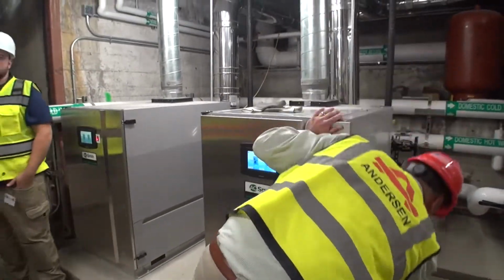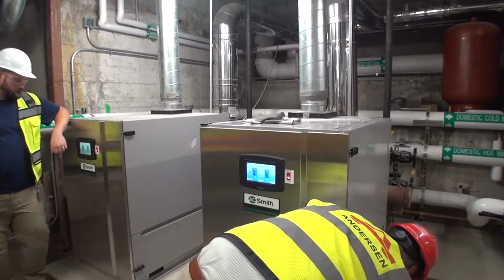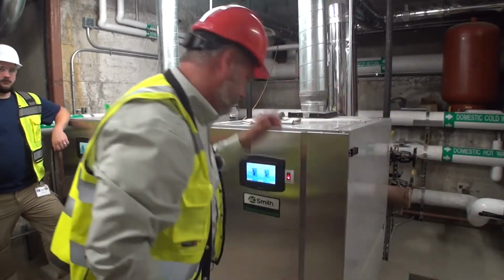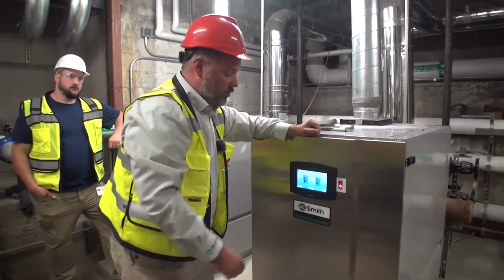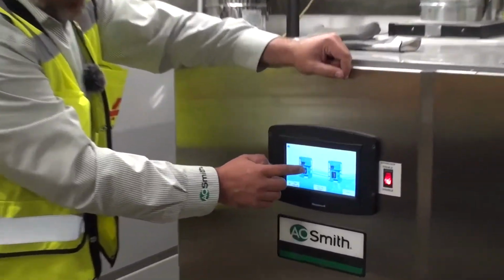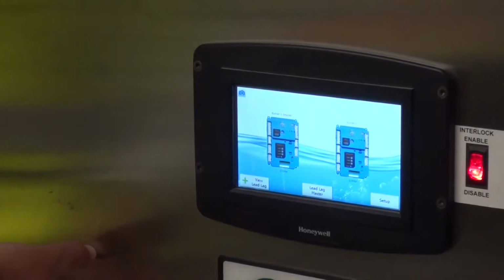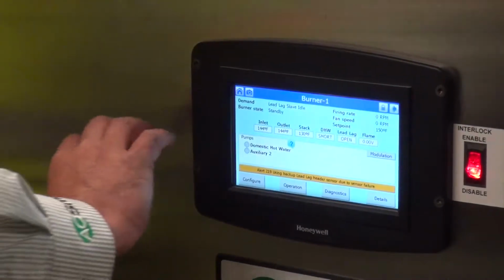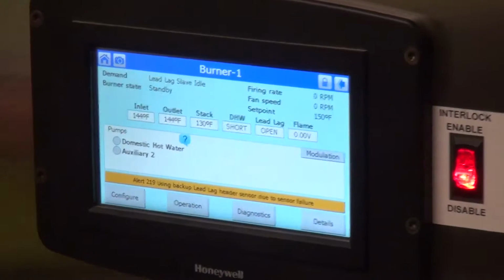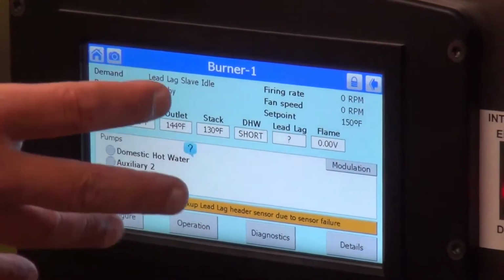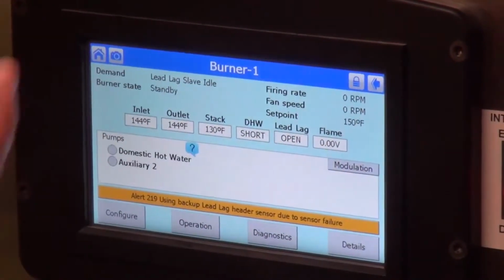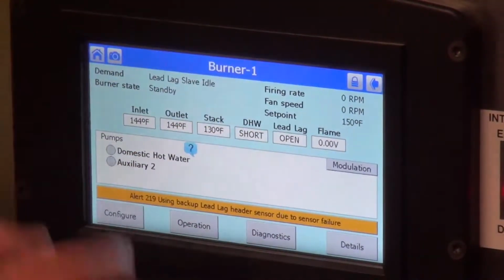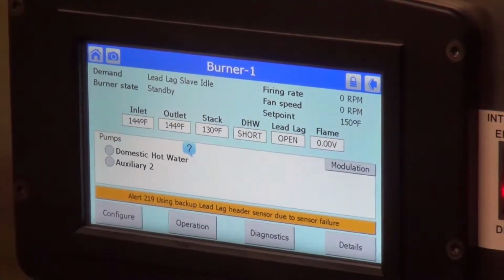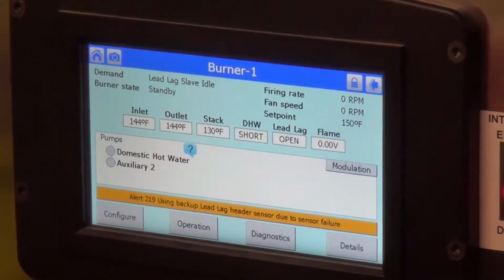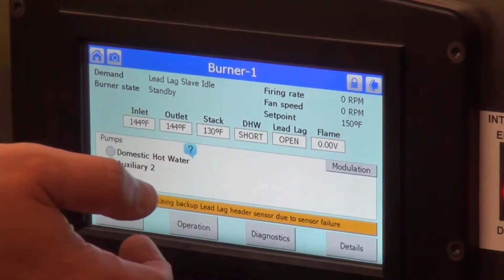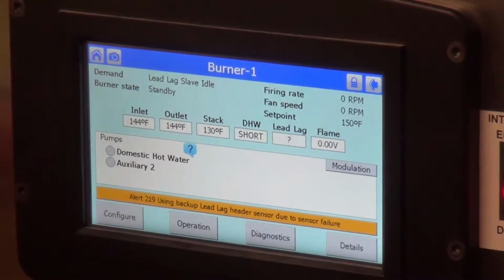They're separate independent controllers, separate independent burners, and both talk to the interface, which talks with the control back and forth. Correct. So if you look at these, each one of these is its own independent control into the burner. So if we click on this, I wouldn't recommend screwing around with it since it's already been touched, but just to show you for an owner's training, each one of those burners has its own control built into this that we can play with if need be. So if you were to service it, we could shut down that burner per this controller, and keep the other one in operation to work with.